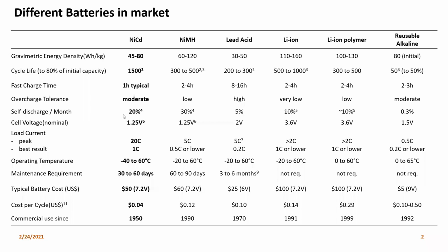Maybe everyone already knows about the nickel cadmium battery, but if it's new to you, let me update you on its construction. Most manufacturers have similar construction. In India, we bought batteries from HPL and also from Alcad from Sweden, and mostly they look similar, even dimensionally, for the same AH rating. The construction is mostly the same: positive plate is nickel hydroxide, negative plate is cadmium electrode, and the separator is a micro-porous polymer used in most batteries. The electrolyte is potassium hydroxide mixed with around 3% lithium hydroxide. If anyone has queries, I can guide on it.